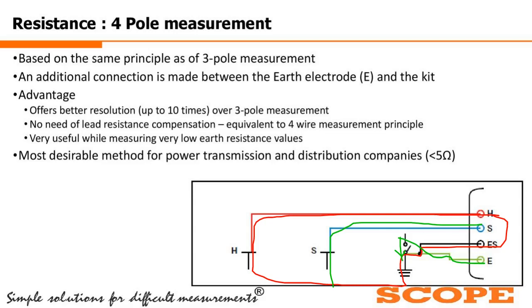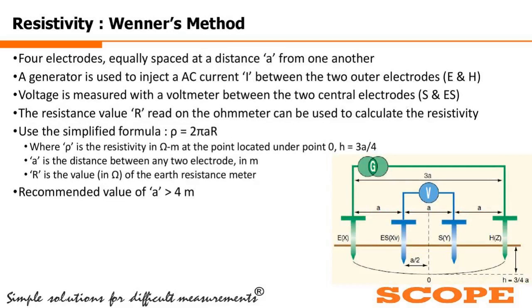It is the most desirable method for power transmission and distribution companies, because it gives very authentic results when we are talking about very low resistance earthing or earth points. For any generation or distribution companies, generally the value of the earth resistance is very low, less than 5 ohm. So it is a very popular method among the discoms, generation companies and transmission companies, where they comfortably and faithfully use the same system of four pole measurement.